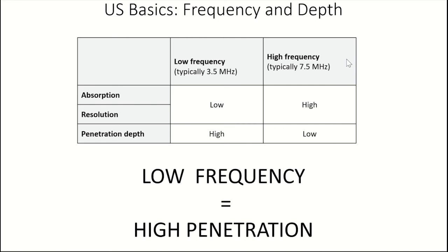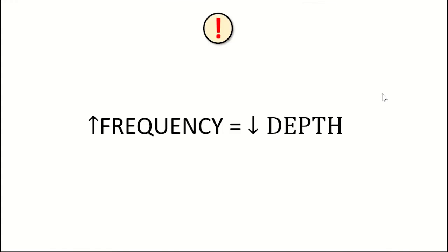Frequency and depth — the basics: the lower your frequency, the higher the penetration, meaning the deeper you get into tissue. They have an inverse relationship. This is so important I'll say it again: penetration, depth, and frequency have an inverse relationship. Increase the frequency and you decrease your depth, and vice versa.